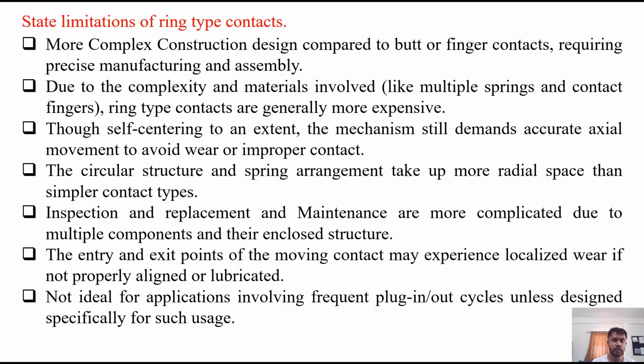Limitations of ring type contacts. So there are several disadvantages as well. More complex construction design compared to butt or finger type contacts, requiring precise manufacturing and assembly. Due to the complexity and materials involved, like multiple springs and contact fingers, ring type contacts are generally more expensive than butt and finger type contacts. Though self-centering to an extent, the mechanism still demands accurate axial movement to avoid wear or improper contact. The circular structure and spring arrangement take up more radial space than the simple contacts, so it requires larger space.